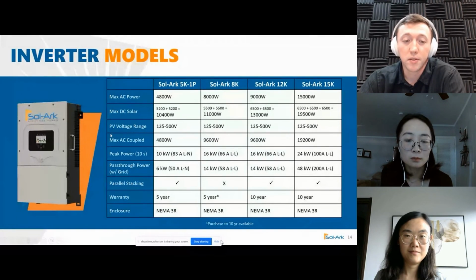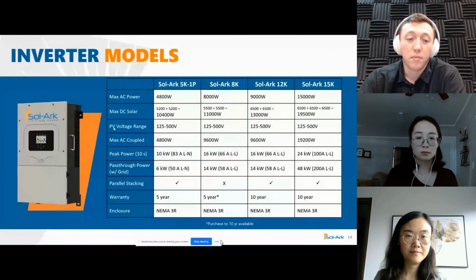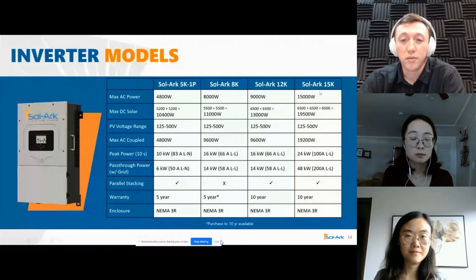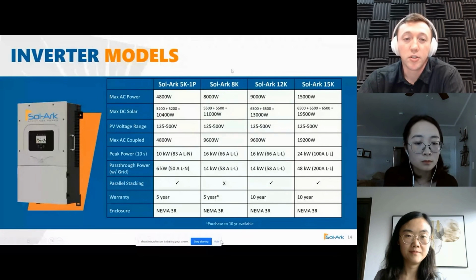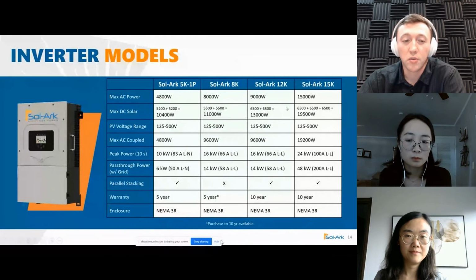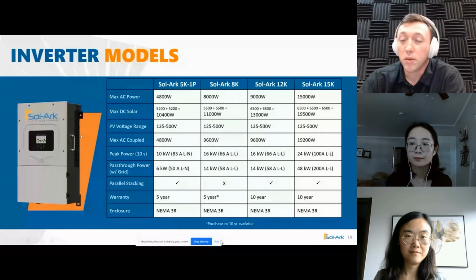What that is basically, if you have a microinverter system or another string level inverter and you'd like to add energy storage into the situation, what we can do is retrofit any one of our inverters, AC couple that directly into our inverter's gen port, and we'll be able to be the controller for that AC coupled input. That means we can control it through frequency curtailment.